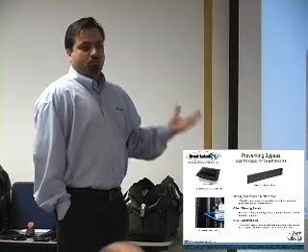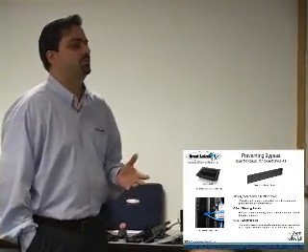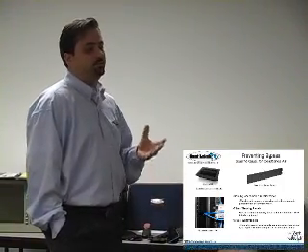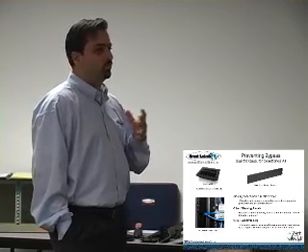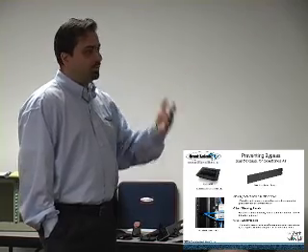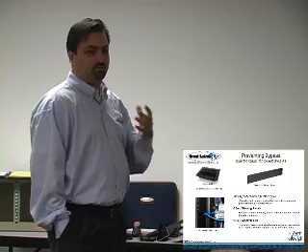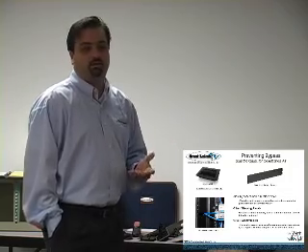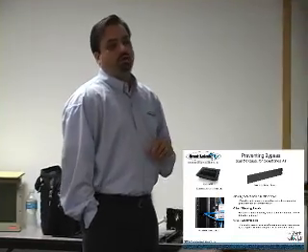Best practices is what we're going to go over. Just real simple, cost-effective tricks and methods to pay attention to and manage correctly. What we've seen in the field is people have open holes everywhere, inside the cabinet, into the floor, into returns, and those are just short-circuiting and simply costing money. So what happens if people keep turning the CRAC unit up and just overloading them?